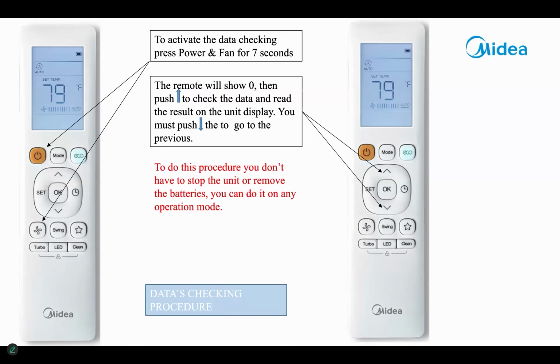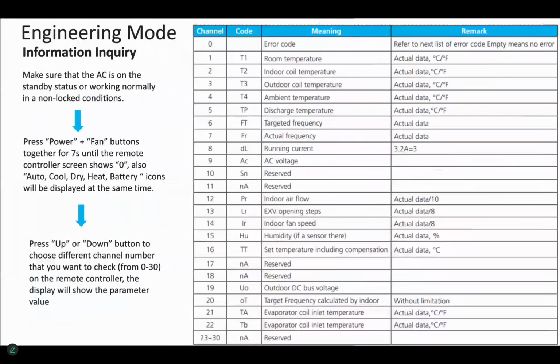What you'll see in the display is 1, 2, 3, 4, 5, 6 for the number of the data. On the display, it will show you the actual data and it will flash it. So if you're looking at T1 and let's say T1 is 71 degrees, it'll show 71 degrees, go blank, 71 degrees, go blank, 71 degrees on the air handler. On the remote display, it'll show 1, as in number 1. Here's the chart. If you get into 0, it'll either show an error code or it'll show NA.